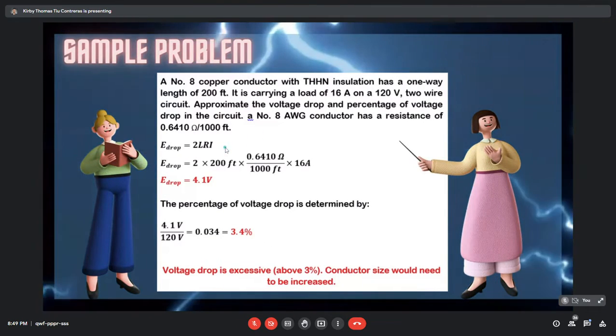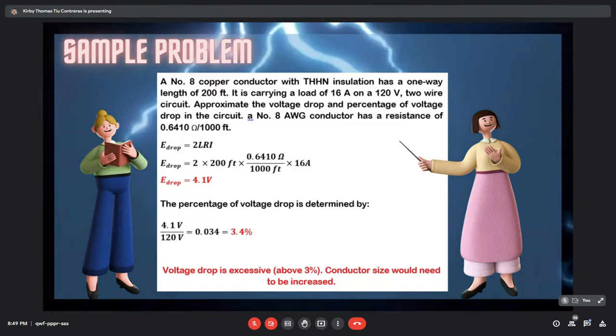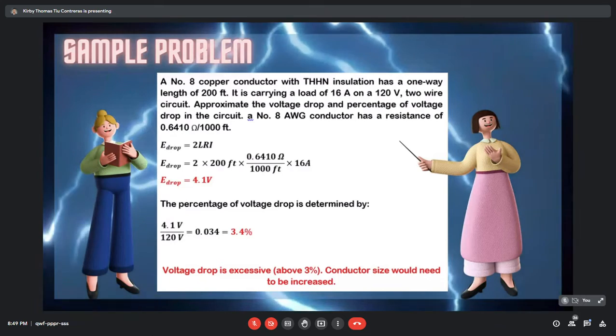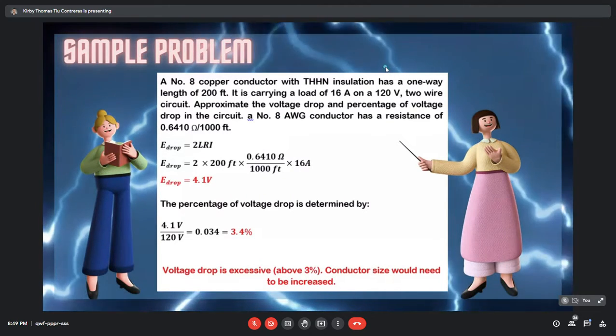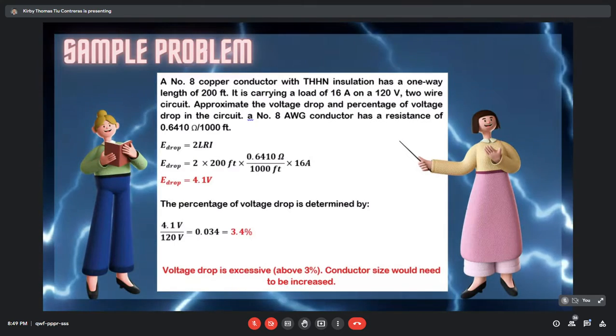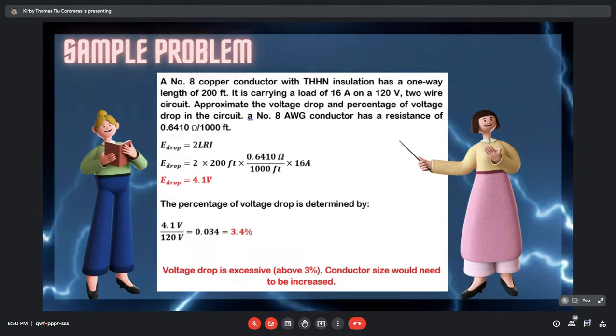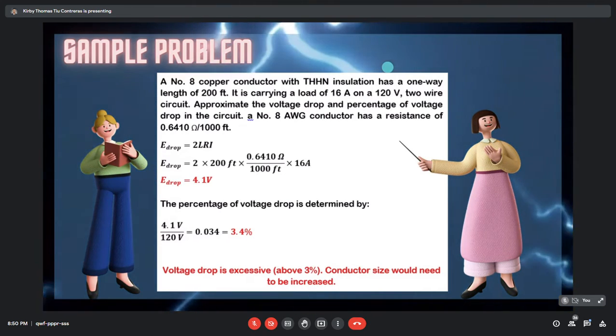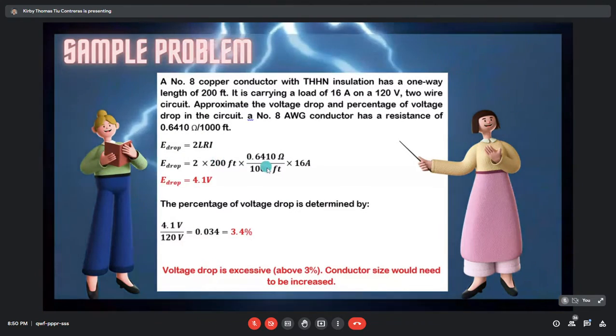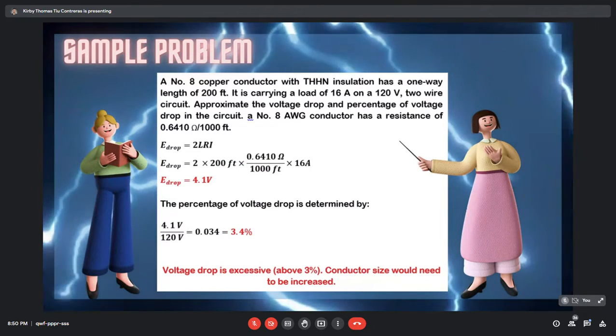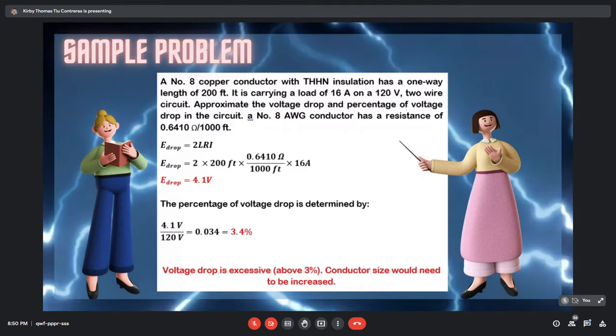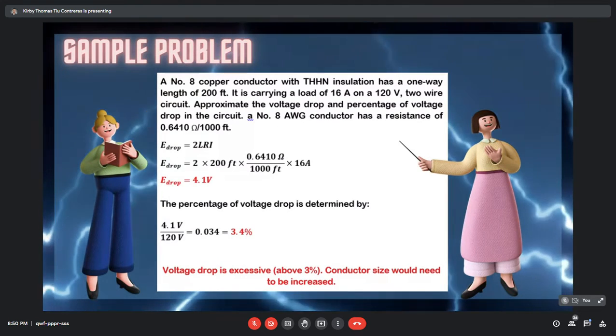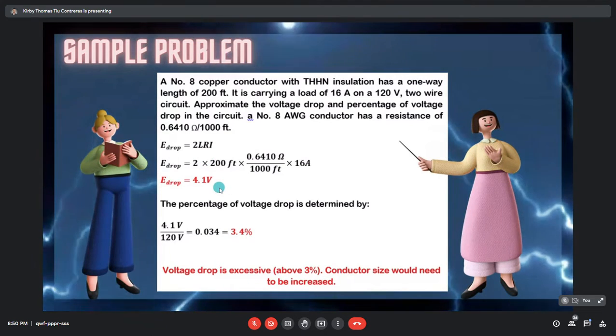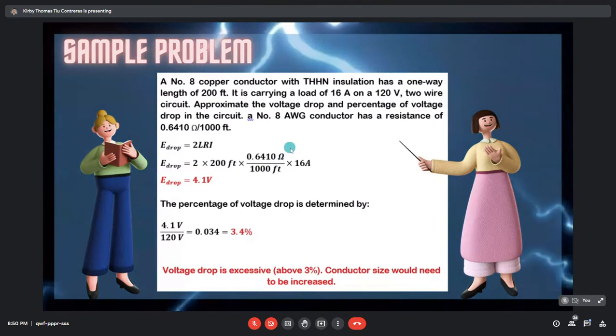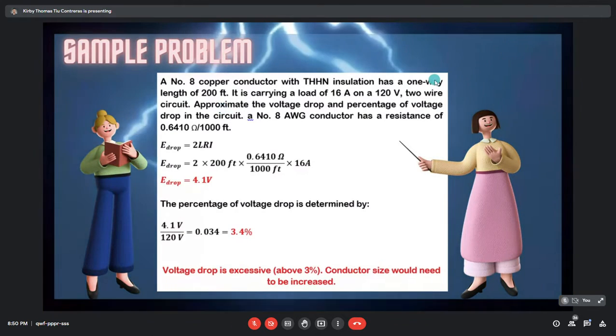Actually, this will serve as a review or clarification from our previous activities. So, just listen. Given the formula, voltage drop is equal to 2L times R times I, where I is the current and R is the resistance. First, convert the resistance, since the given number 8 AWG conductor has a resistance of 0.6410 ohms per 1,000 feet. We multiply by 2 here since the given length is one way, so it should be two way. That's why we multiply by 2 here.